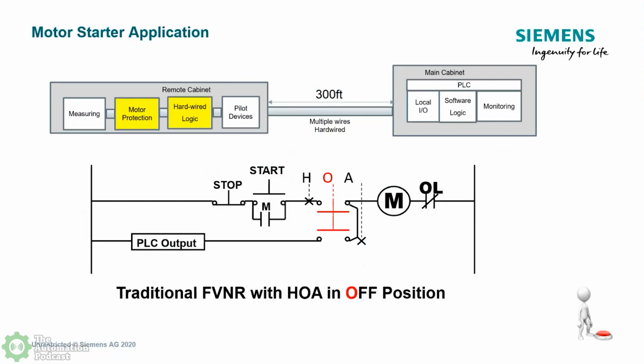To kind of fall back on the old ways, I've been around in this business for quite a few years, but back in the day we had a simple hand-off-auto start-stop station for a traditional full voltage non-reversing motor, and that could be attached again to a fan or a conveyor or a pump. And then you had the control system in big gray boxes, and you had all the wiring coming out and so forth. And you may have had some hand-wired logic in the motor control bucket or the motor control cabinet. And then of course you had your protection. In the old days when we were still using abacuses, we had the motor heaters, which were bimetallic pieces of metal for your overloads. But now everybody's using solid state motor overloads.